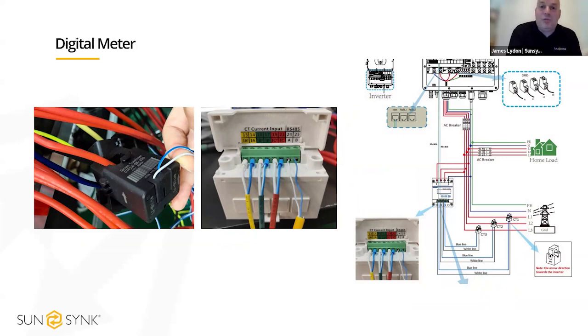But if it's a longer run, or if it's on one of the 3-phase high voltage systems, we would always recommend using a digital Eastron meter. That's connected back to the inverter on a full patch lead, so we're not having to join the CT, we're not having to extend the cables, and this is going to prevent any losses in the comms from the CT back to the inverter. So Segen do have our single phase and 3-phase Eastron meters available.